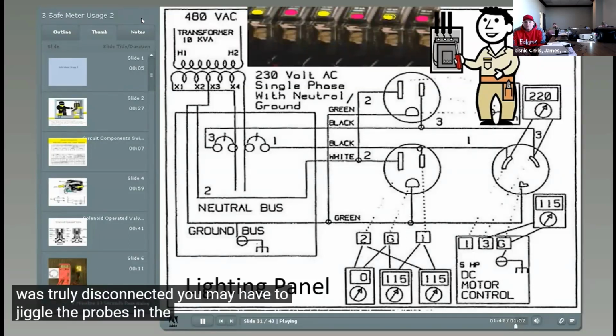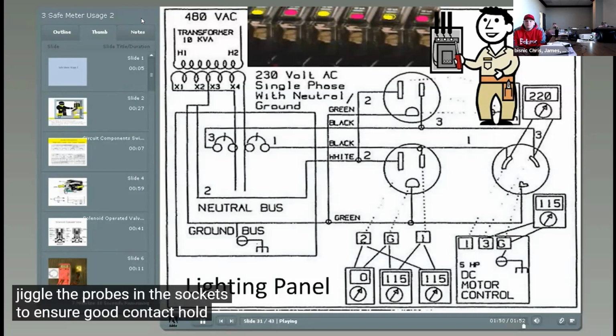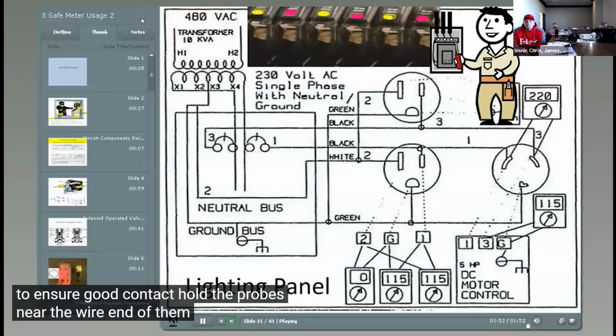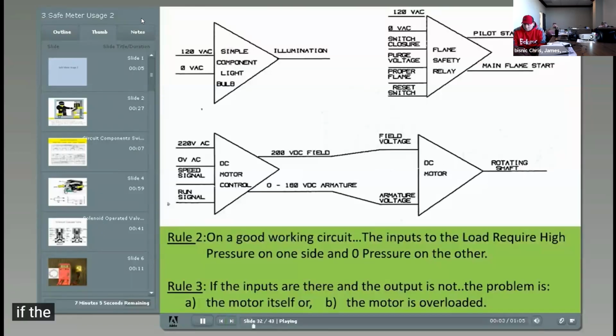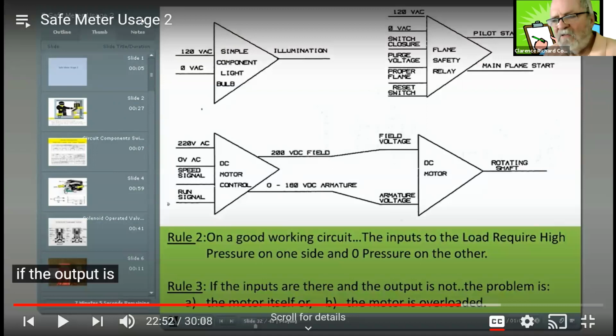You may have to jiggle the probes in the sockets to ensure good contact. Hold the probes near the wire end of them. Notice they said hold the probes near the wire end of them. Sometimes when we're doing these electrical things in the classroom setting, these guys would have their fingers down there at the bottom of the probe, very close to the metal tips. I'm going, you don't need to be there. And he says, get your hands at the end of the probe where the wire cable's going and be doing some touching that way. Now, do not be part of the circuit. Don't get so intimate with that circuit is what I was telling these guys.